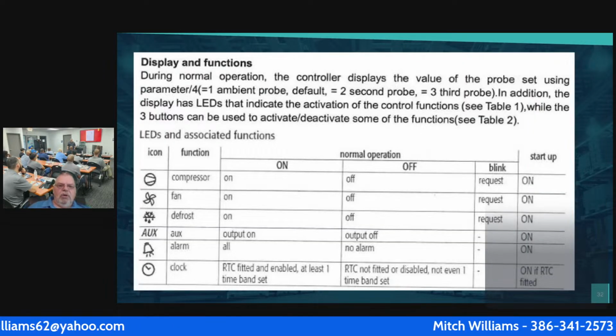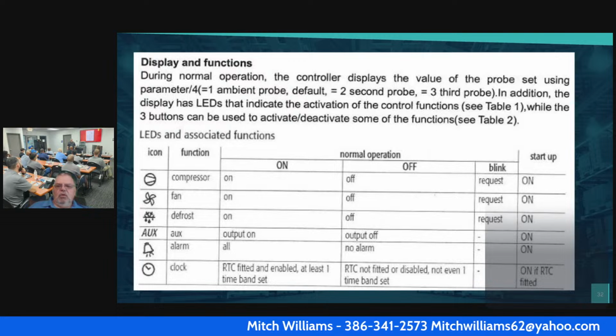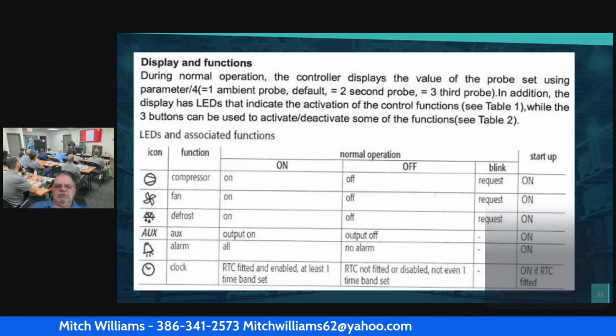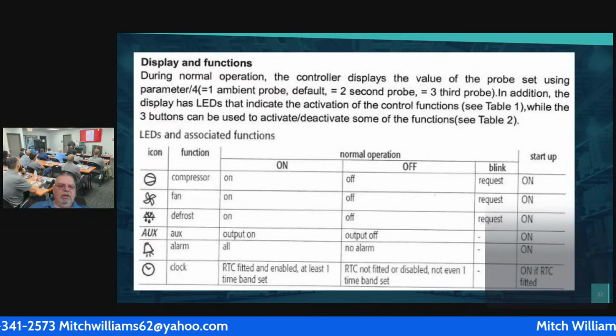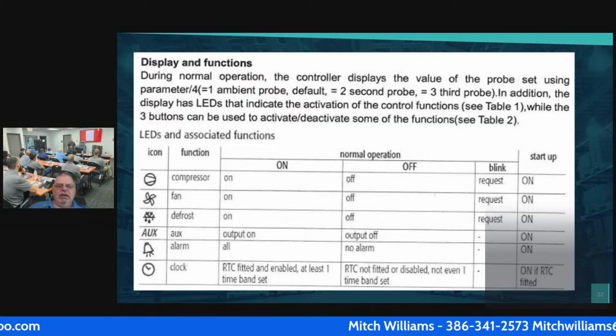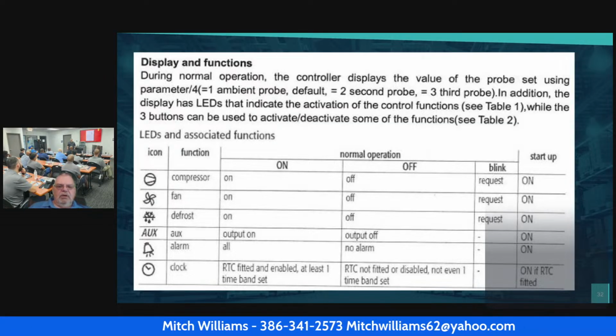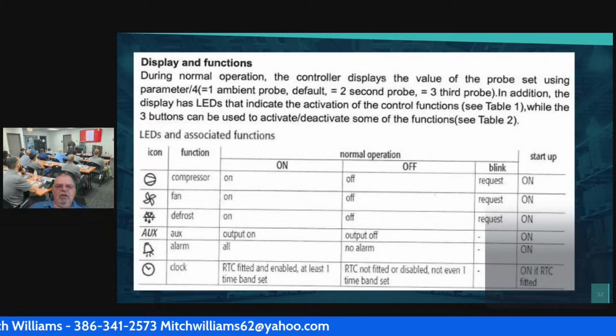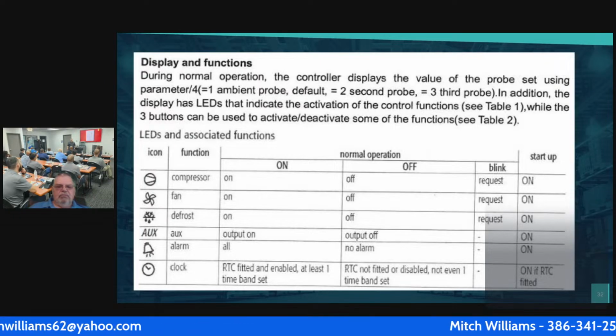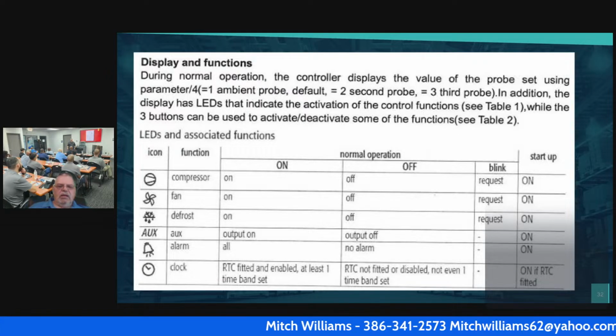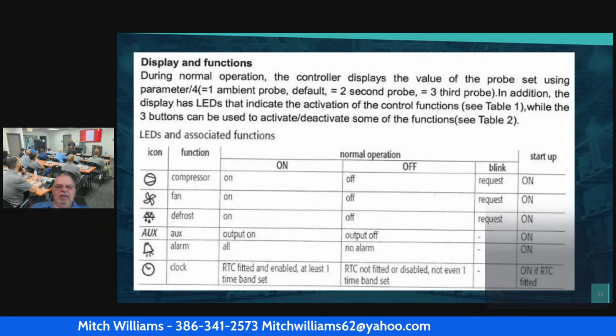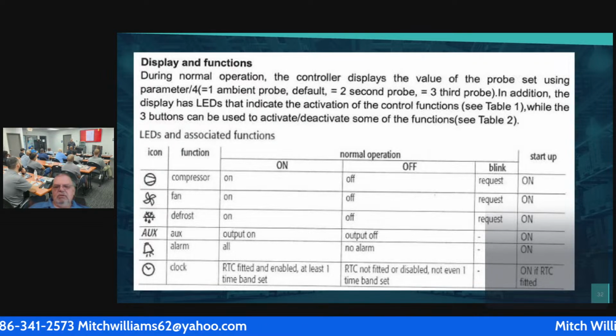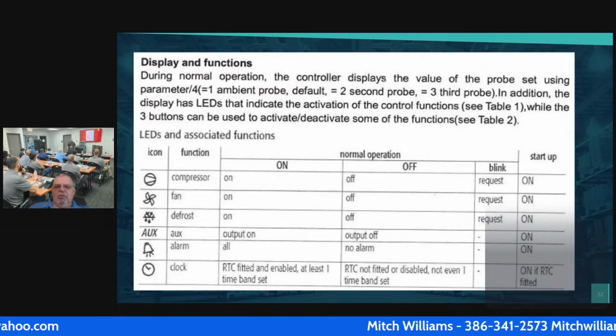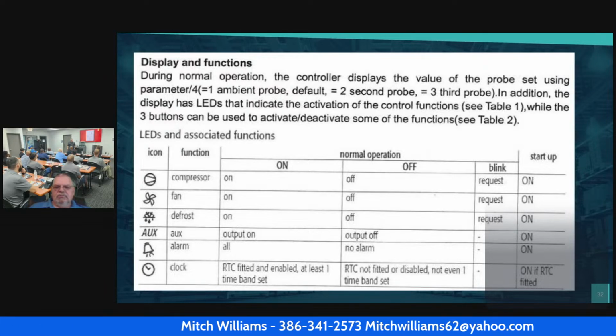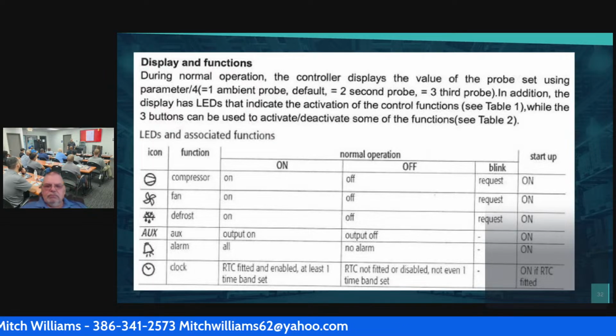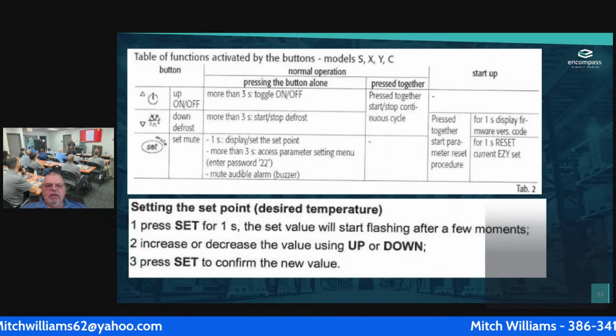Okay, so here's table 1. Display functions: compressor, normal operation, on, off. If it's on, the compressor should be on. If the fan's on, compressor should be on. If the defrost is turned on, it should have that interval change. Okay. The auxiliary input is on. If it's off, if I have an alarm, that should be on. The clock, the RTC fitted and enabled, at least 1 time band set. If it's off, of course, all of them are off except the RTC. Okay. Here's the rest of that table.